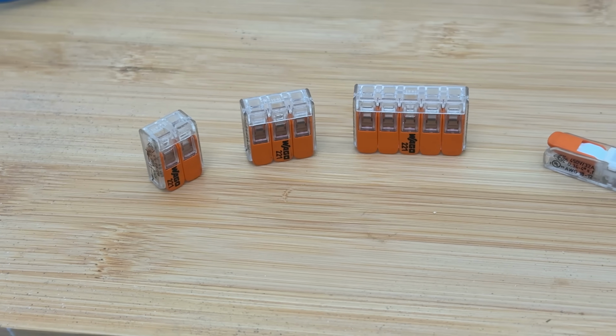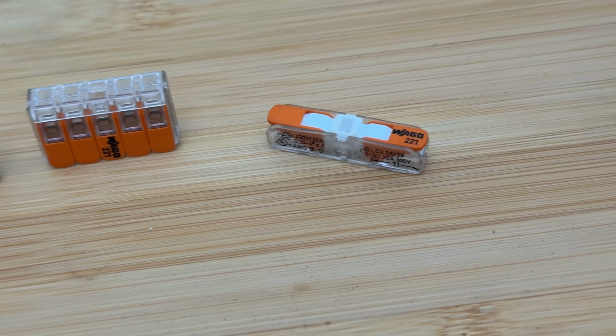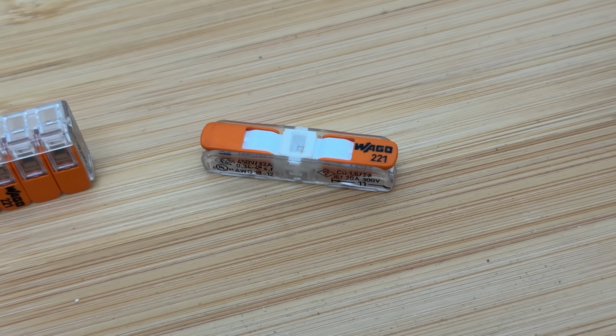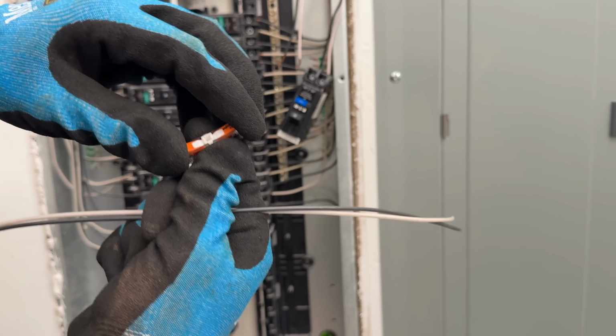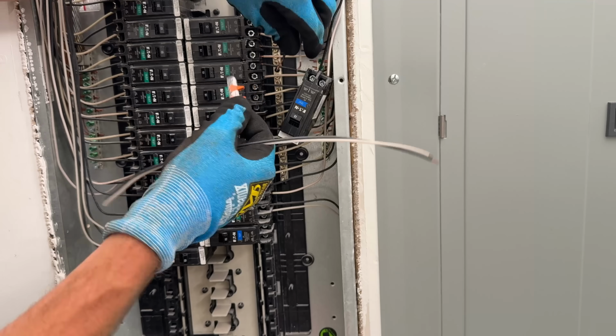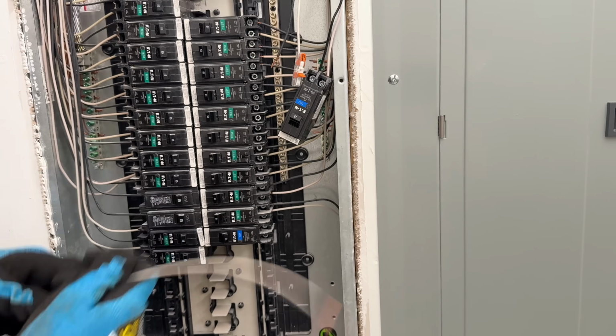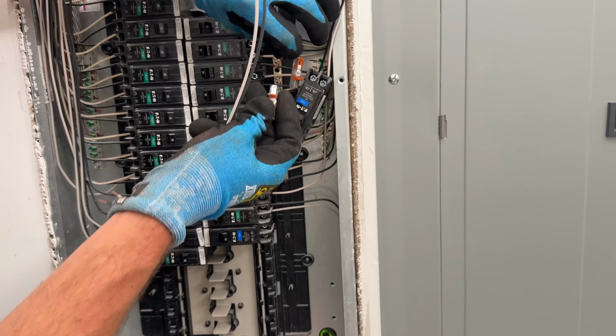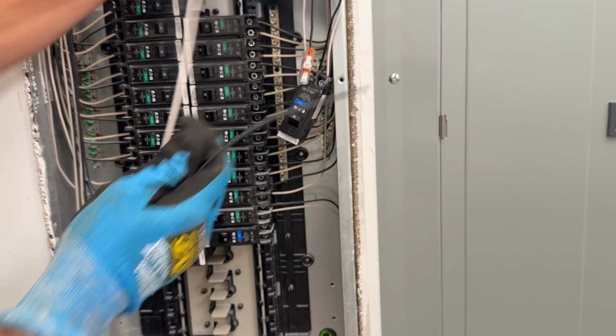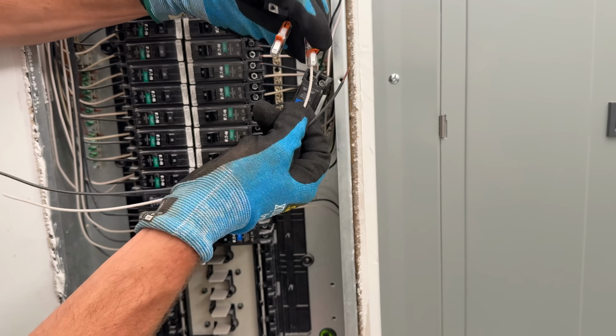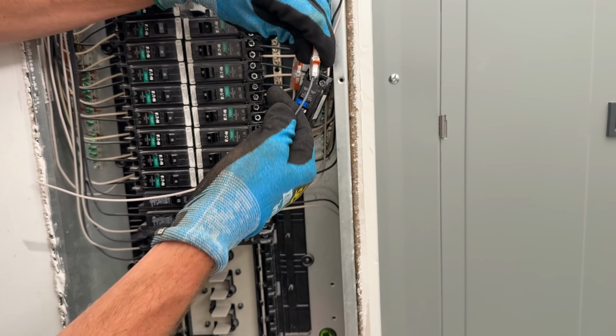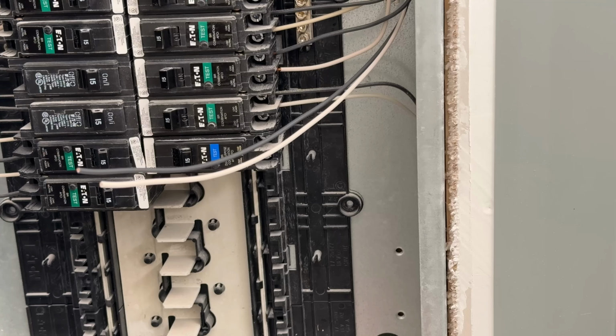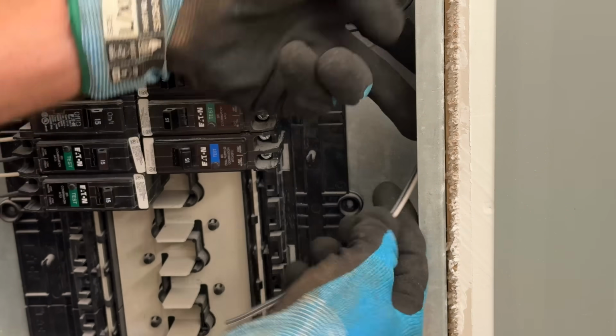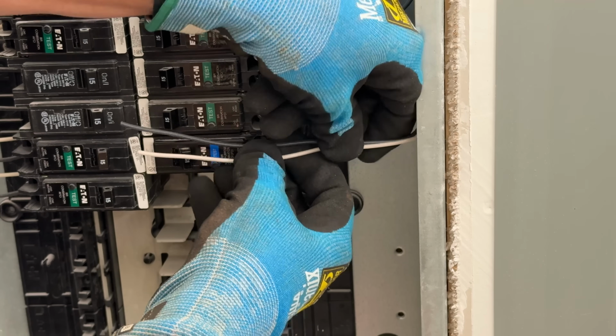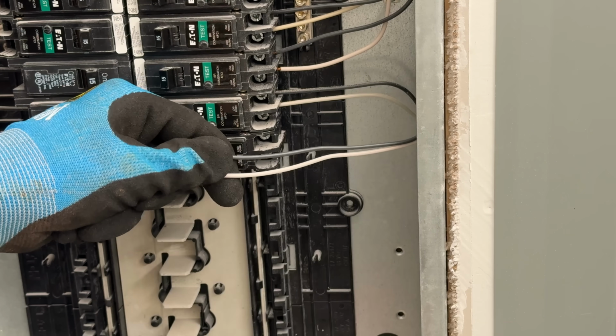We're going to use Wago 221 lever nuts. By far the best, not the 2-wire, 3-wire, 5-wire, but this inline splice. It is perfect for this application. Why? Because it's compact and it lets the wire pass through the splice. And since our service panel is a large junction box, you should be okay in your area, check your local code, to have splices within your box without any issue, so we can just extend those out to the new location and get our routing down, seeing what we need for our final length.